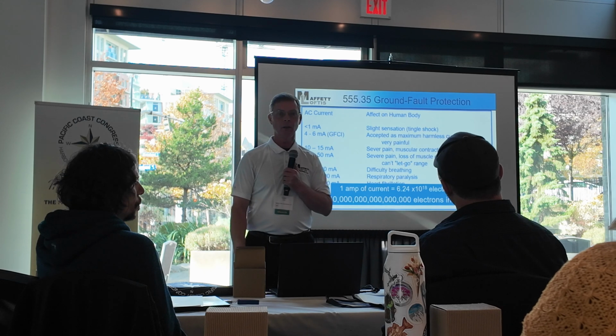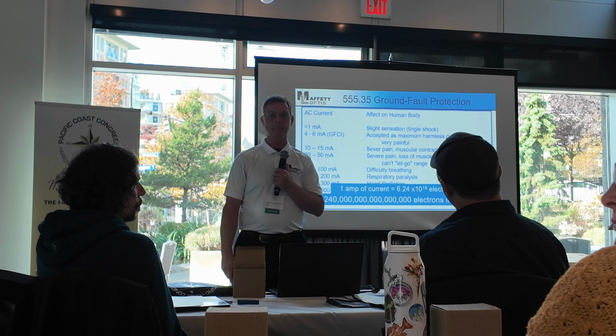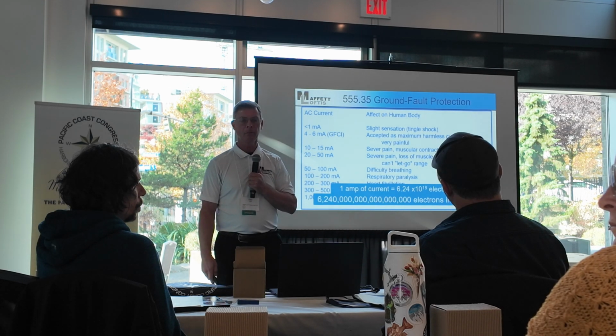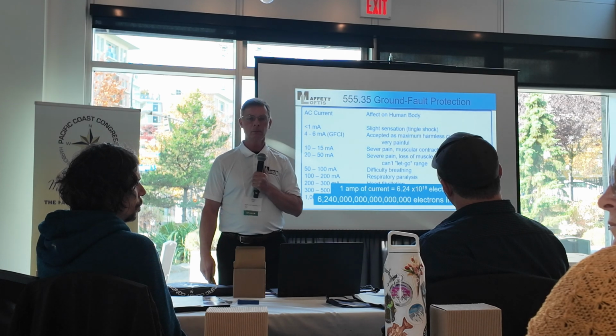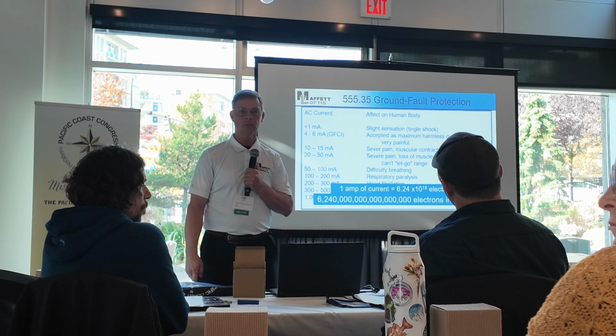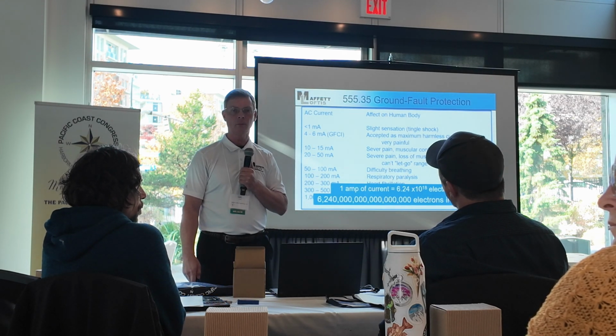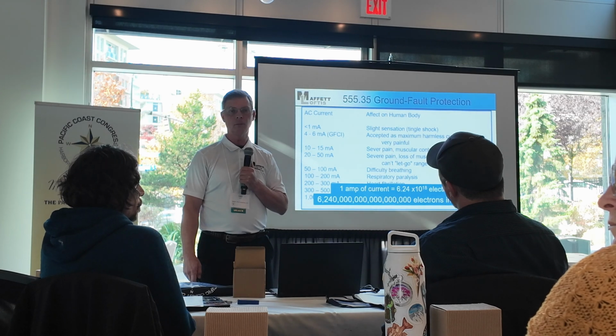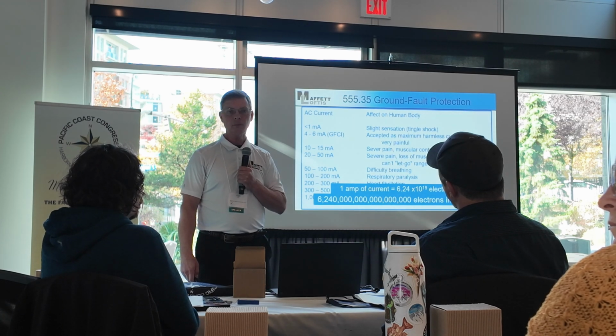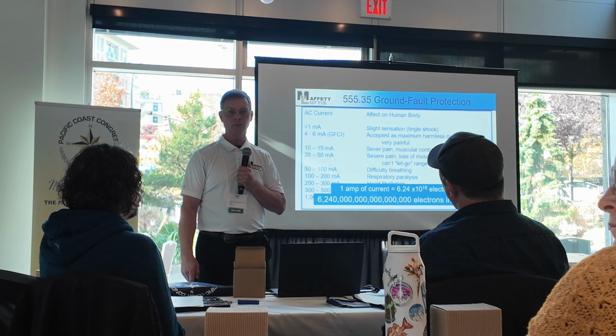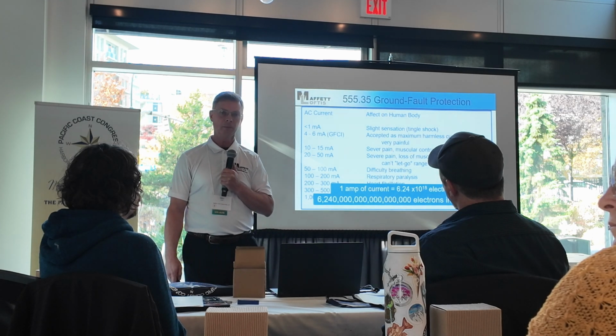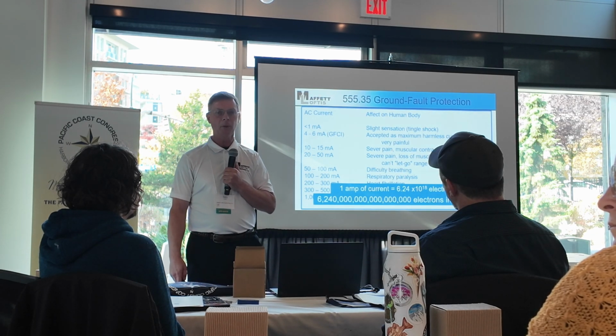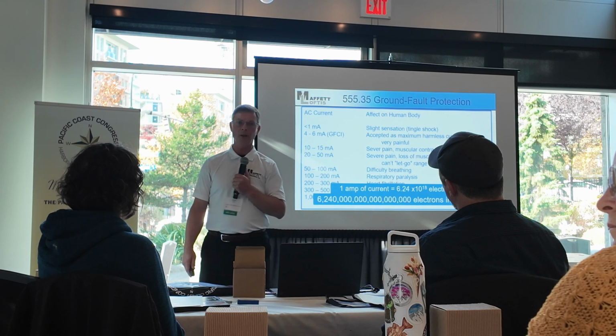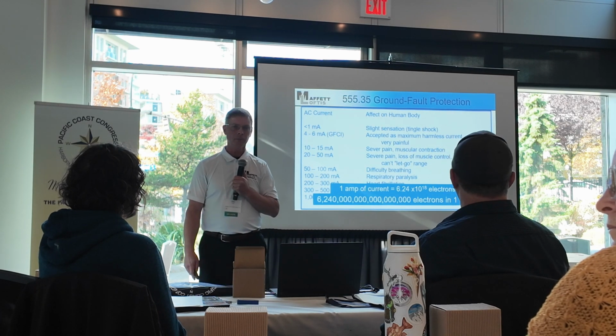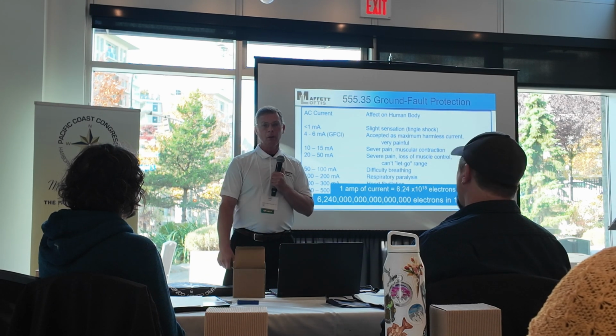Yeah, I can attest to this one. It doesn't matter which marina it was, an install that we did for the pilot. Our leakage monitor was detecting that it was significant, over 230 milliamps. But the person said, "Oh, well, let's try that boat. Let's verify." They threw one of those things in the water, no beeping. But it could be grounding. It was still a ground fault. It's still a false sense of security, and if you get between that and where it's grounding out, you'd be in potential danger.